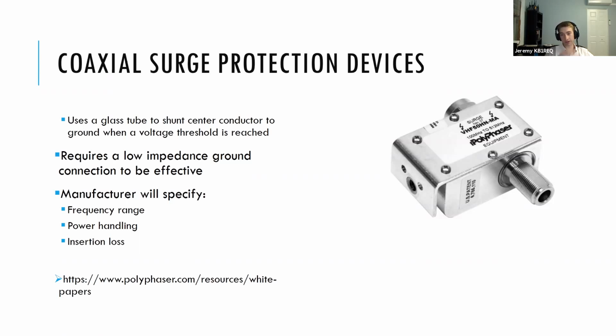So that's why I said, if you keep your equipment connected, you want to make sure that it's also well grounded, because there is going to be some surge current coming down from the surge protector, and you want to give that a preferred path to ground. Because if you don't, it is still going to find a path to ground for that remaining current, whether it's through control wiring, or the wiring back through your power supply and AC to your AC ground, which travels through the walls of your house or building back to the panel, right?